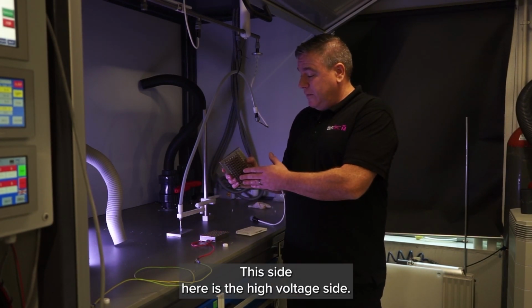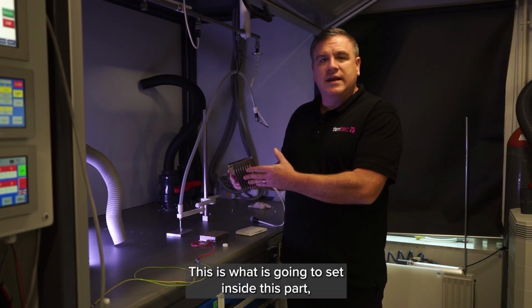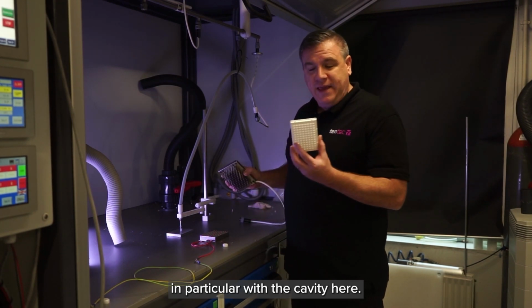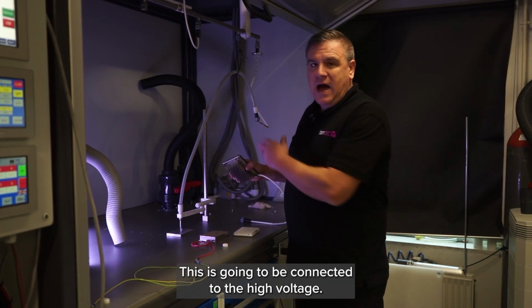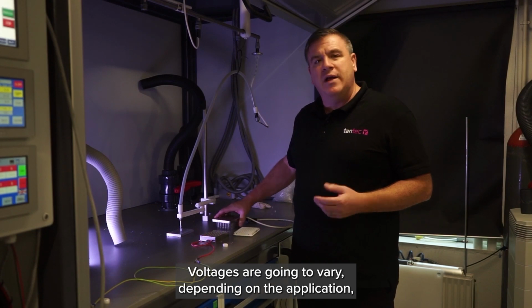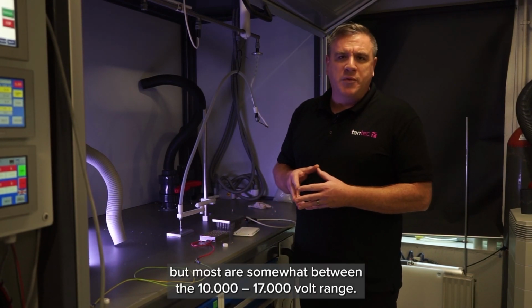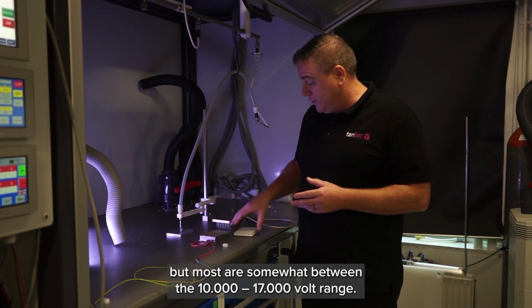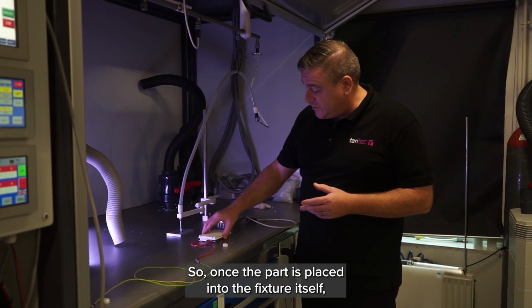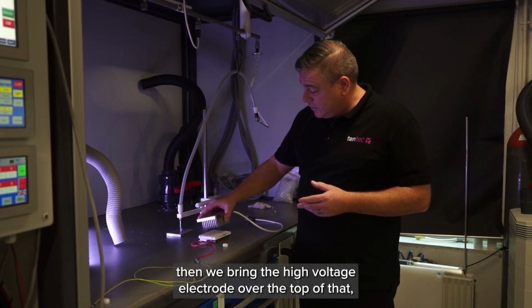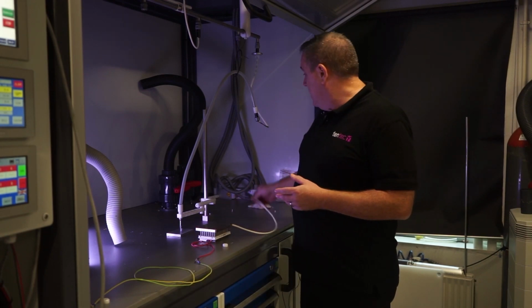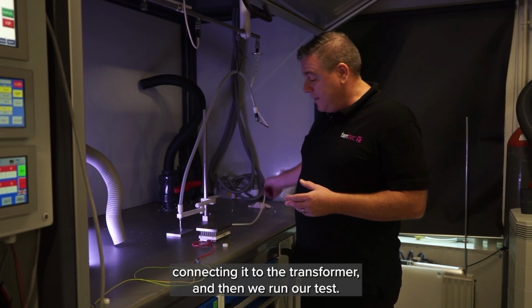This side here is the high voltage side. This is what's going to sit inside this part, in particular with the cavity here. This is going to be connected to the high voltage. Voltages are going to vary depending on the application, but most are somewhere between the 10 to 17,000 volt range. So once the part is placed into the fixture itself, we bring the high voltage electrode over the top of that, connecting it to the transformer, and then we run our test.